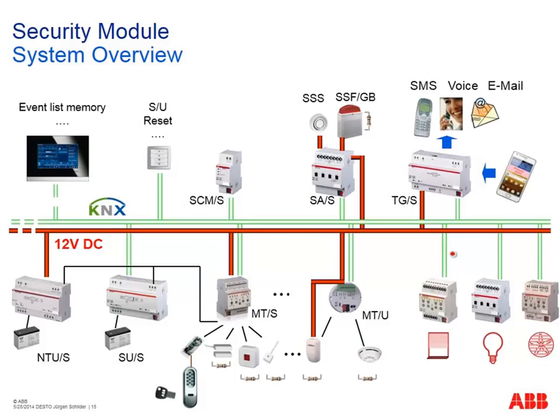Here is a more comprehensive display of the solution including power supplies. The green line is the KNX bus and the red line shows the 12V DC network. The security terminal, siren, strobe light, and telephone gateway all need 12V. Using the 12V uninterruptible power supply with a battery buffers the entire 12V network, ensuring the whole system — including alarming — works even during mains failure.